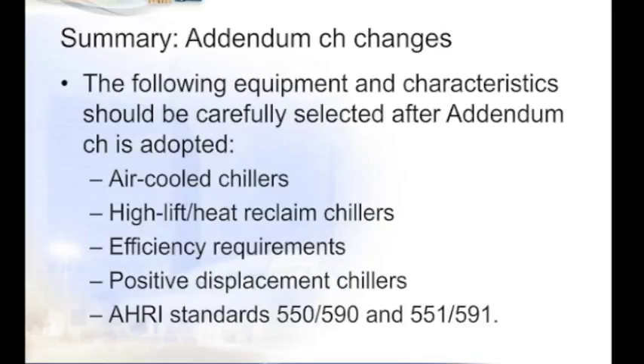And then finally, a quick list of what we want to review for the changes that are going to be adopted when 90.1 Addendum CH is in effect January 1, 2015. The changes include increased chiller efficiencies and adding requirements for various chiller types. Air-cooled chillers now have multiple compliance path options. Chillers operating in high lift and heat reclaim applications are excluded. Water-cooled positive displacement chillers now need to match the efficiency requirements of water-cooled centrifugal chillers.